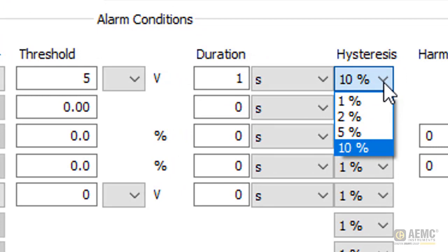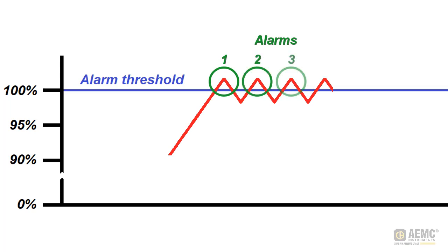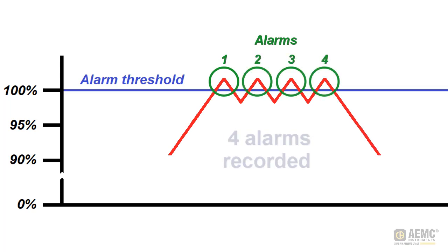To understand how this works, consider an alarm with no hysteresis. The instant the trigger threshold is exceeded, the alarm activates and deactivates the instant the measurement falls below the threshold. In this situation, multiple alarms may be recorded if the measurement is very close to the threshold. Each time the measurement fluctuates slightly above and below the trigger, a separate alarm is reported. This can result in multiple alarms being detected for what is in reality a single spike event.